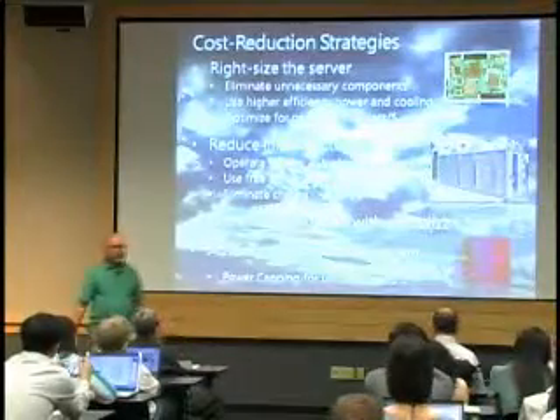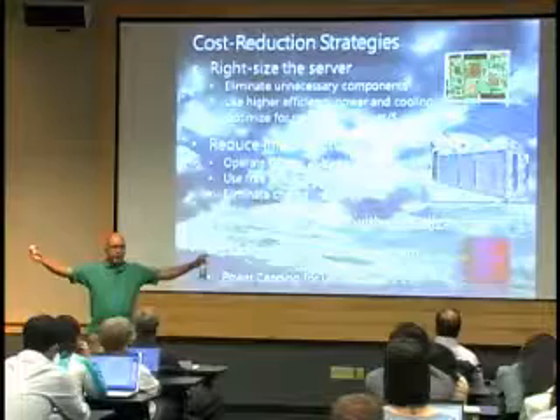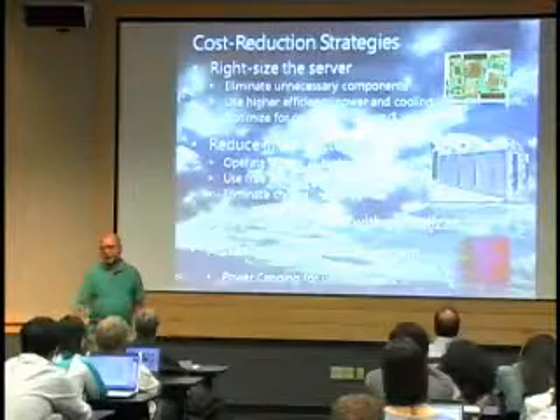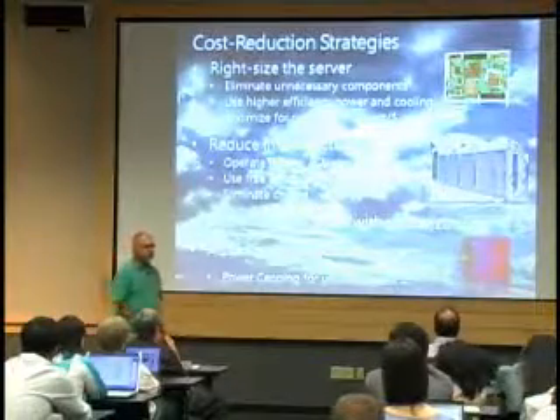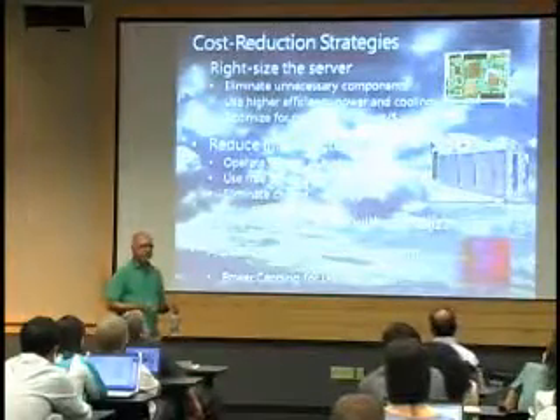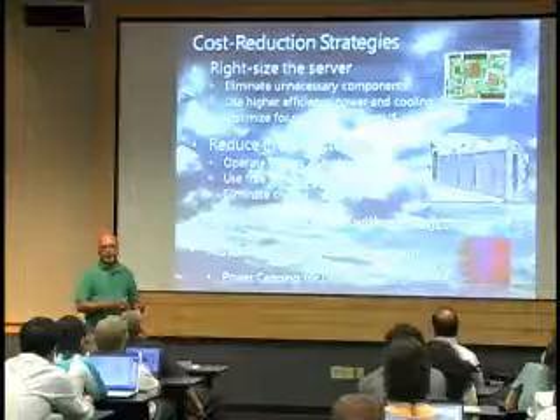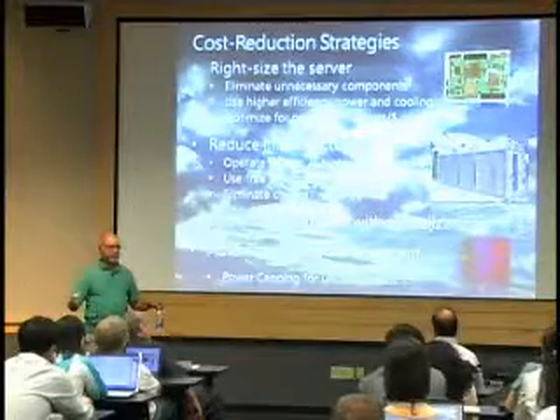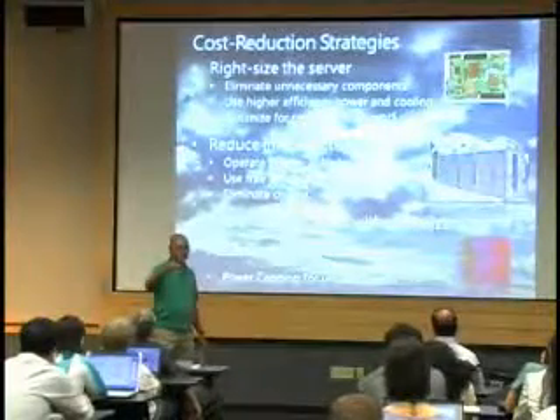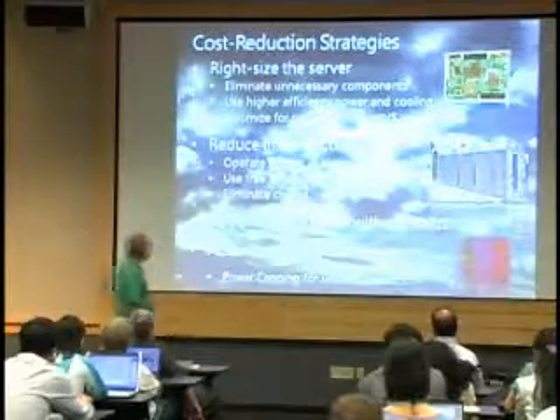That was simple. Then when we looked at a lot of these platforms, they were designed to serve a set of needs that were pretty wide, so they had lots of PCI slots, lots of memory slots. We knew how much memory we needed, we knew how much I/O expansion we needed. So we had them remove those things, which reduced the board size, gave us higher density, and lowered our cost. It also allowed us to use smaller power supplies, because typically when you have all these expansion slots, the power supply is sized for the maximum possible configuration, and now you have a 700 watt power supply operating at 200 or 250 watts. It's not operating at its most efficient operating point. So those are just some examples.